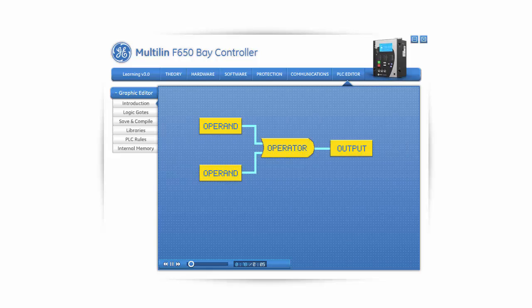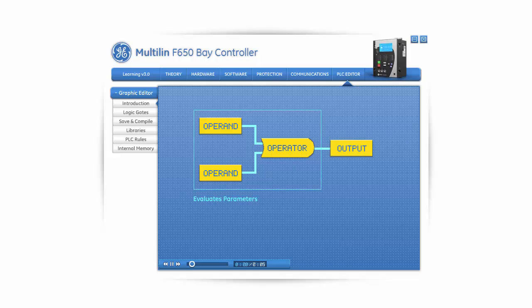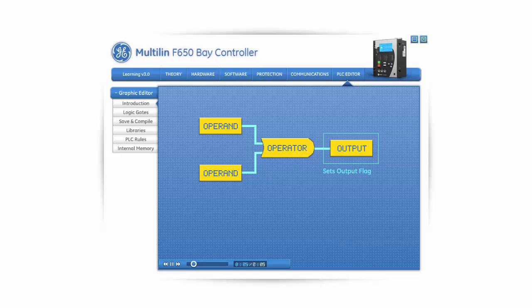Each logic equation consists of operands, an operator, and an output. The operator compares all of the inputs assigned to it and then sets an output that is based on the status of those inputs and the function of that particular gate. Each logic equation evaluates the parameters and then sets an output flag. The operands can be inputs, outputs, or protection or control elements of the relay. The operand can have a logic state of zero or a logic state of one.